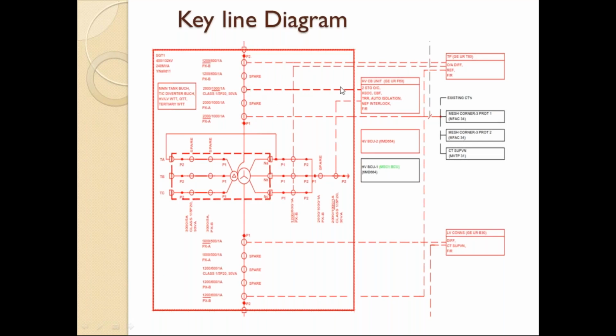This is a circuit breaker, and we have given that this third core will be a CB unit, and this one is the spare. This core may be used for bus bar protection. This area may be double bus bar protection, or maybe a mesh corner protection. If it is a single bus bar, then single bus bar protection. Depending on that protection, we select the CTs.